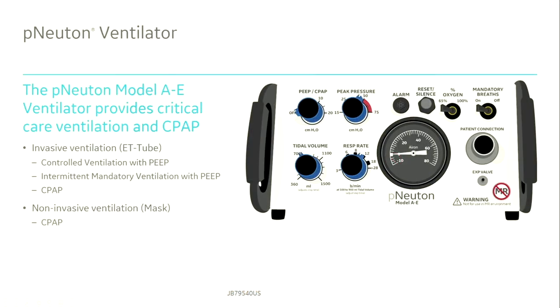The pNeuton A-E is a pneumatic ventilator designed to ventilate critically ill adult and pediatric patients 50 pounds or greater. The modes of ventilation offered on the pNeuton A-E are controlled mandatory ventilation, CMV, intermittent mandatory ventilation, IMV, continuous positive airway pressure, CPAP, and pressure limit. The pNeuton A-E has easy-to-use tidal volume and rate controls with built-in CPAP and can quickly be set up and operated. Clinical uses for the pNeuton A-E include inter- and intra-hospital transport, including use in the ER, special procedures, and disaster management planning.